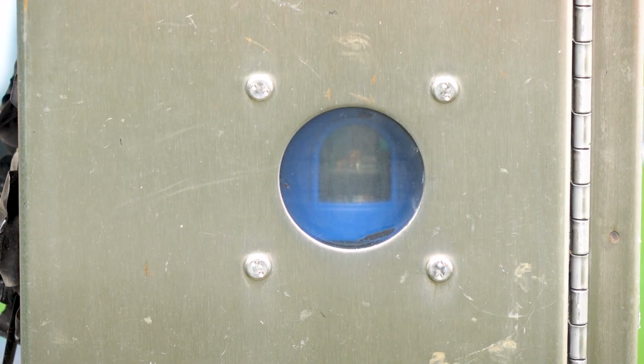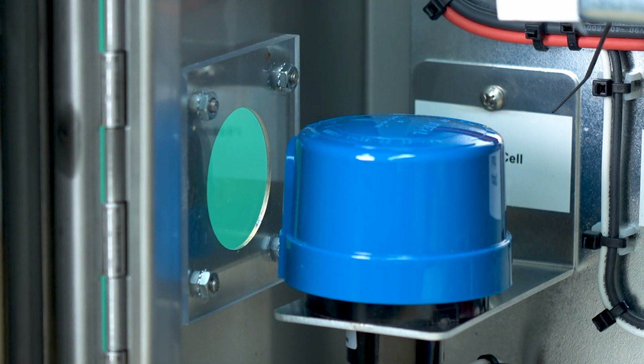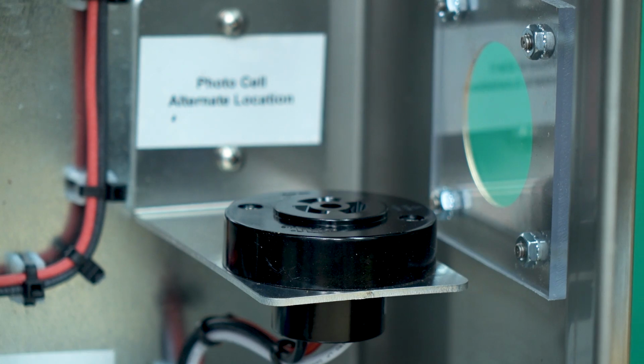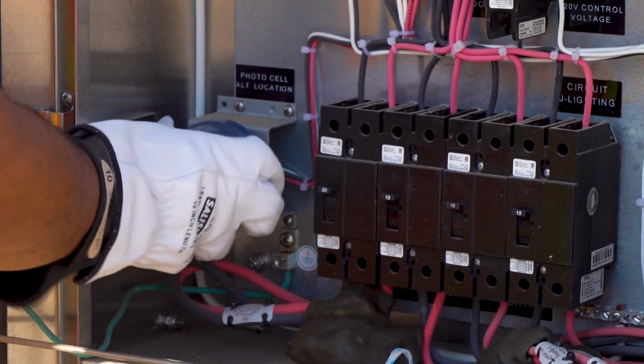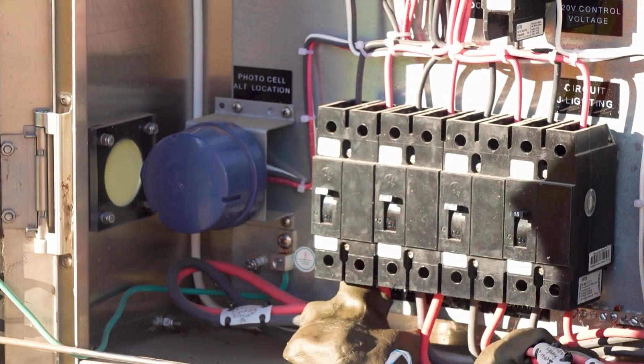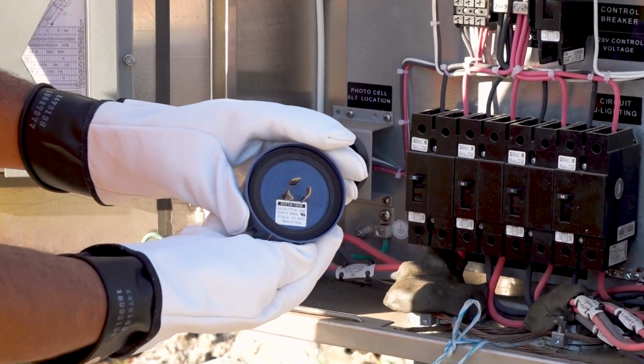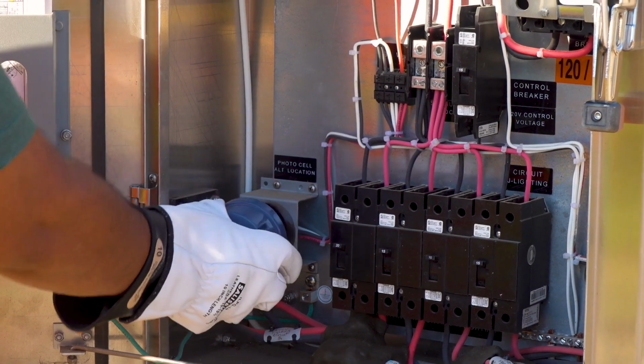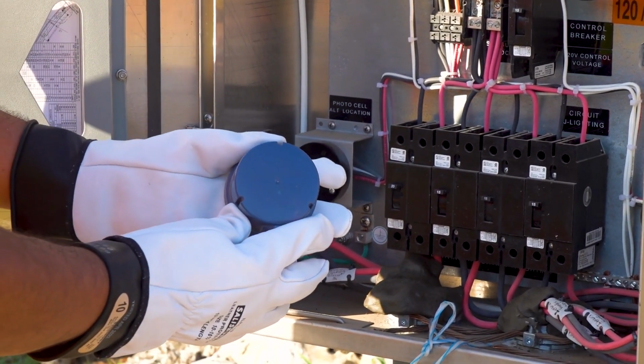When the photocell is specified to be installed within the service enclosure, the UL panel shop should provide 2 photocell viewing windows, one on each side of the enclosure. These windows allow for quick and easy field relocation of the photocell if a local light source interferes with proper operation of the photocell. The photocell is attached to a special receptacle that facilitates quick replacement. To inspect a photocell mounted in the enclosure, the inspector can remove it by rotating its housing and then pulling up and out of the socket.